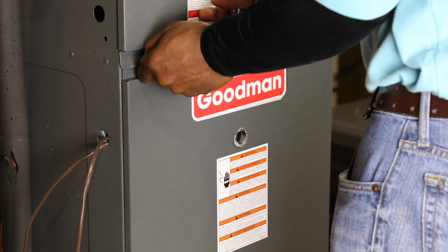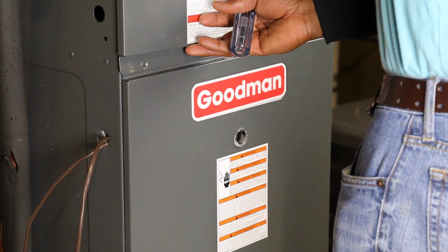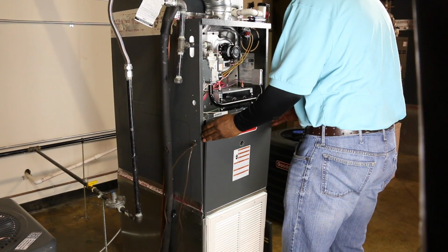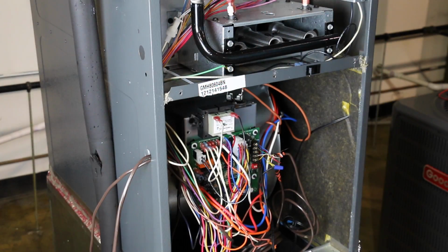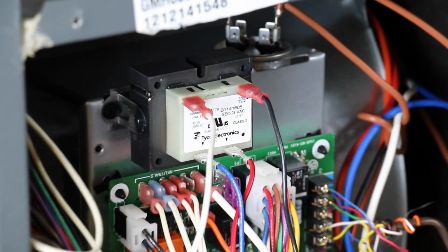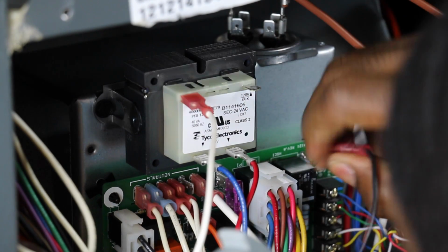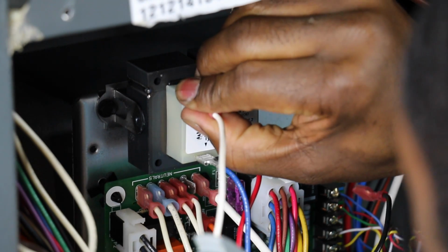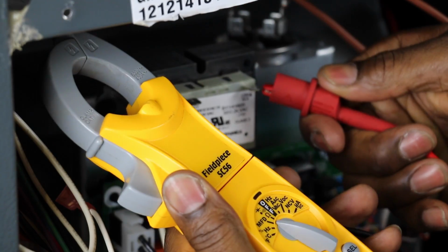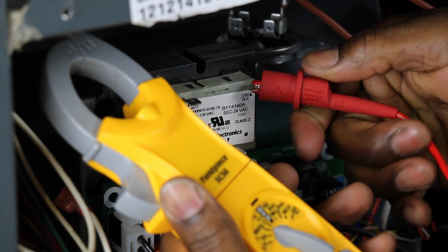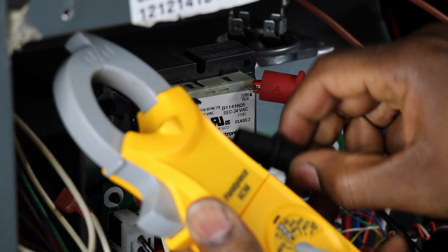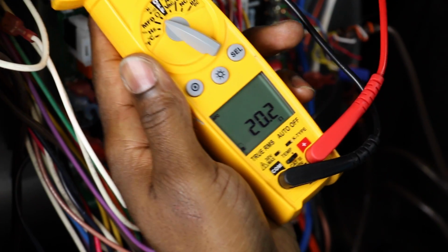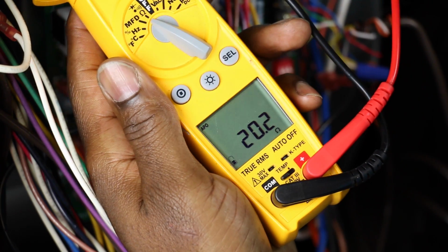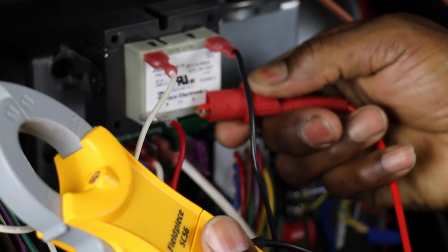The transformer is almost always located at the indoor unit. On a gas furnace, you'll typically find it in the blower compartment. Remove the power wires to isolate the primary. Using alligator clips with this meter will ensure a good connection on the transformer. This is a 120 volt transformer, so you'll note that the primary side is 20 ohms.